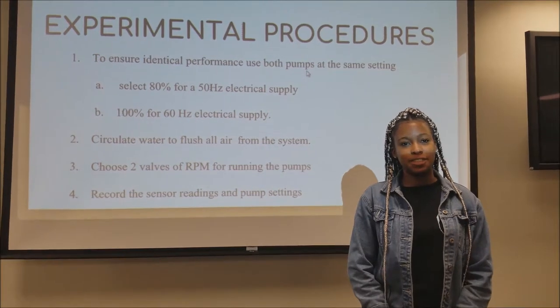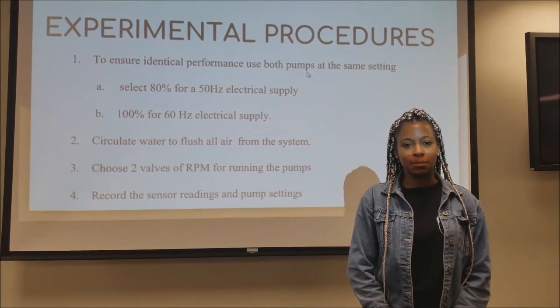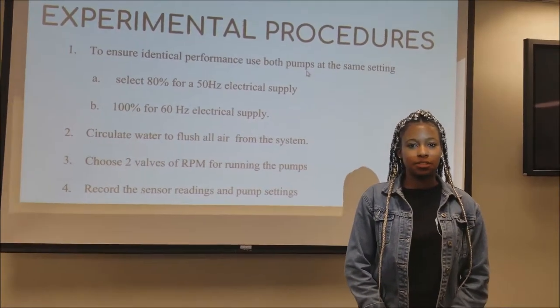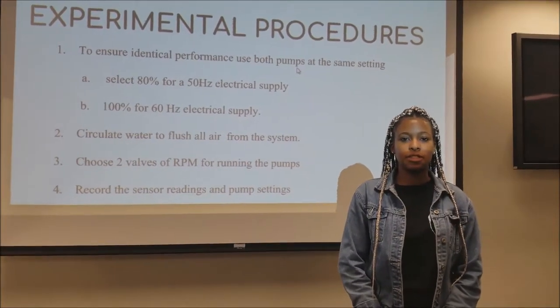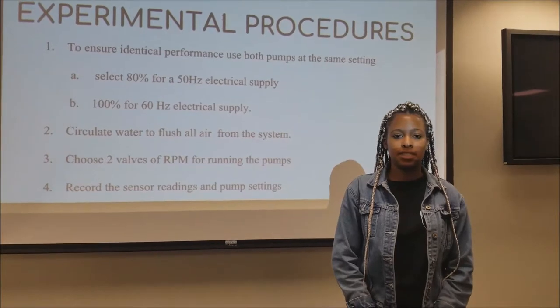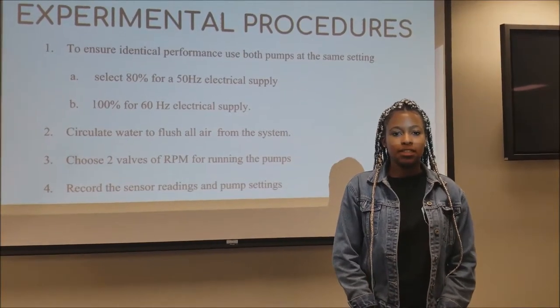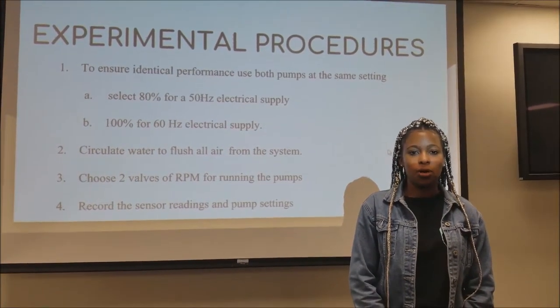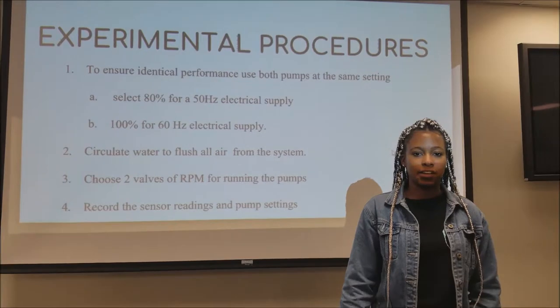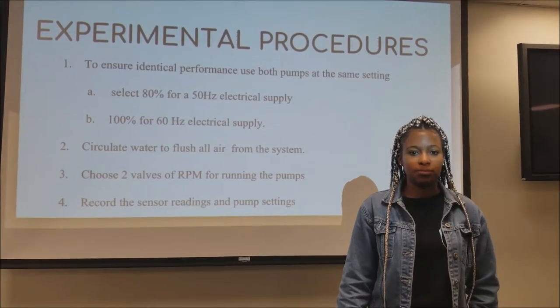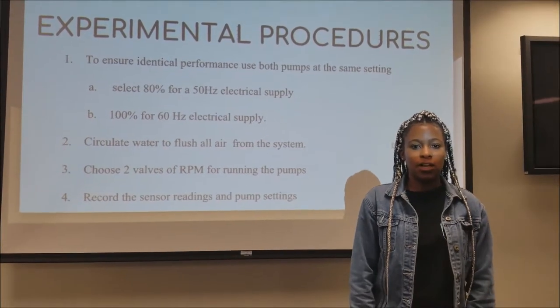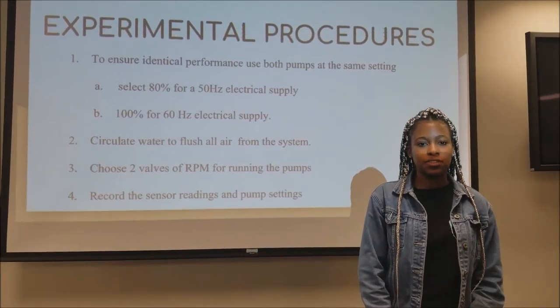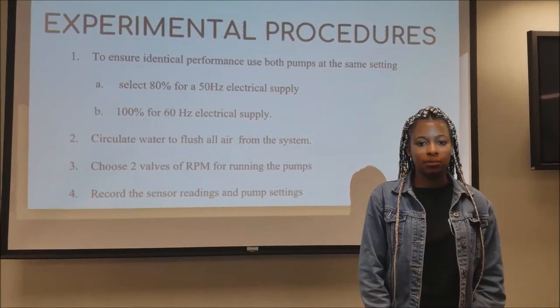The procedure for running centrifugal pumps in parallel: to ensure identical performance, make sure both pumps are at the same setting. The second step is to circulate water to flush the air from the system. Next, choose two values of RPM for running the pumps.